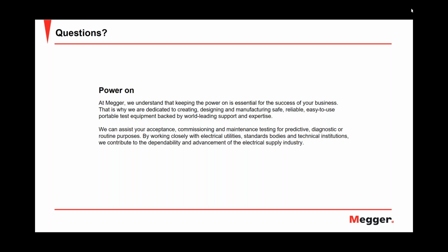Depending on the equipment you have, more modern equipment has this insulation resistance function built in, even in an automated way. So if you connect your 3 cores, you can measure all 6 pairs, the 3 phases to the neutral and the 3 phase-to-phase situations at once, and you get in a few seconds a very clear picture of what's going on. So phase comparison can be used.